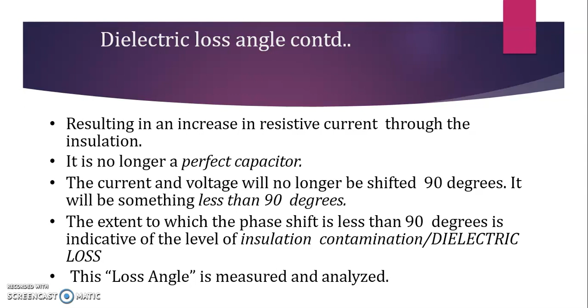Now the extent to which this phase shift is less than 90 degrees is called the dielectric loss, or it is an indication of the level of contamination. To what level is the insulation damaged or contaminated? This loss angle is measured, and then we draw some kind of analysis from this loss tangent.